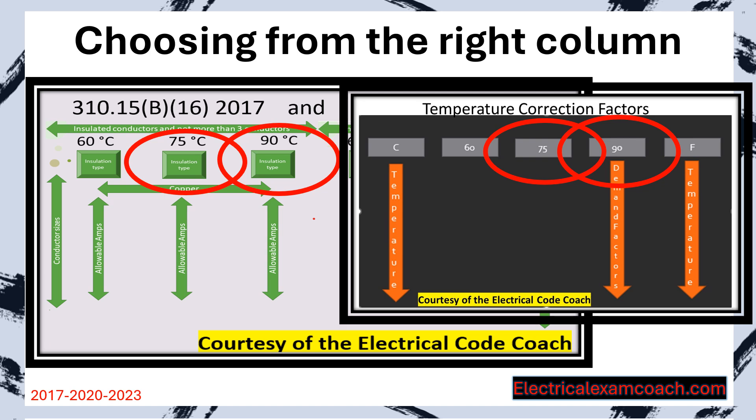One thing I want to mention at this point is NM Cable, which is Romex — that's just a trade name, along with Southwire and others. In the codebook it's called NM Cable. For the purpose of bundling adjustments and temperature corrections, you are allowed to choose from the 90 degrees C column when doing those calculations.